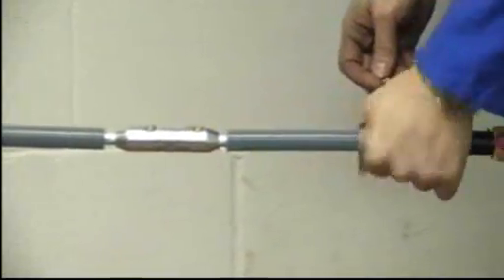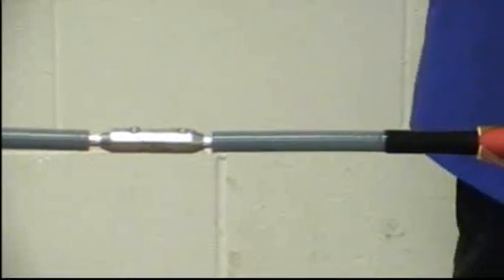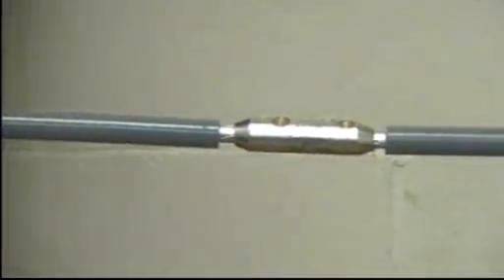Before proceeding, de-grease the connector and the primary insulation. And then apply the stress control tape, with half width overlap and stretch, filling in the gap between primary insulation and connector, and across the length of the connector, as shown.